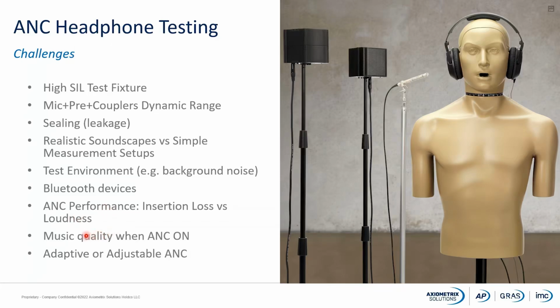The audio playback can be deteriorated when the ANC is turned on. Then again, the ETSI standard has recommendations about how to measure this. And last but not least, particularly the newest ANC devices will come with adjustable or adaptive ANC that might change over time depending on changes in the environmental noise. And once again, the ETSI standard gives us some recommendations on how to perform measurements for this type of ANC.